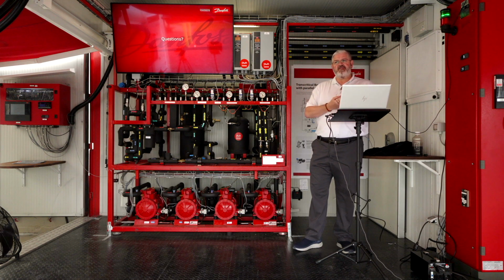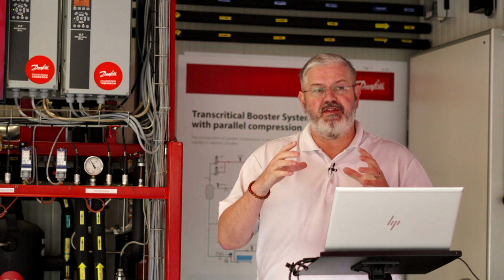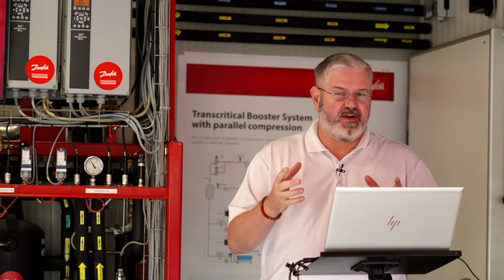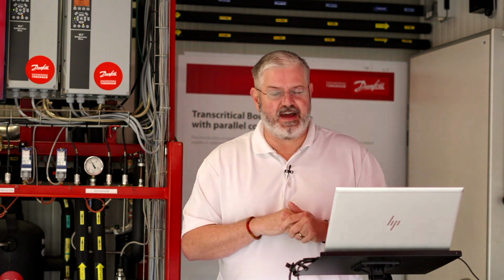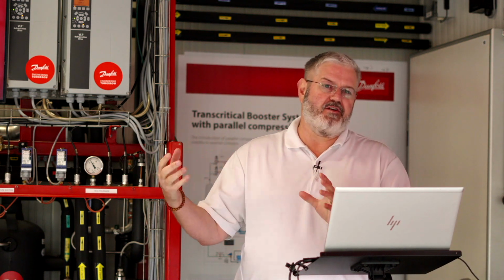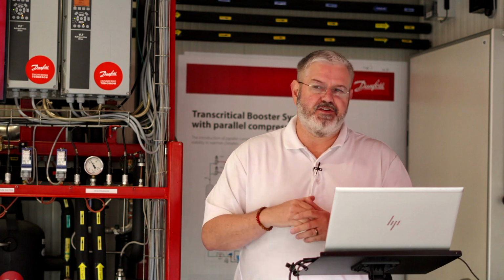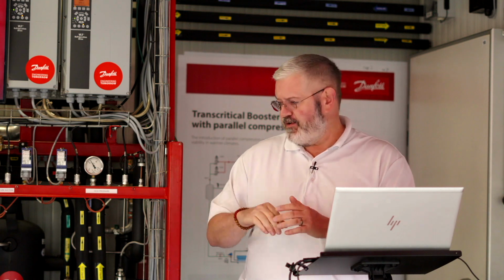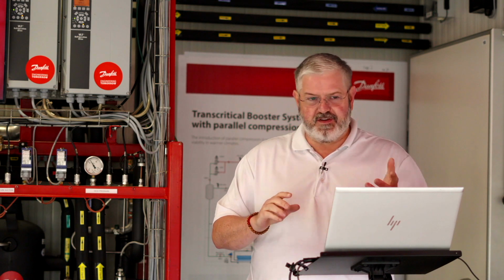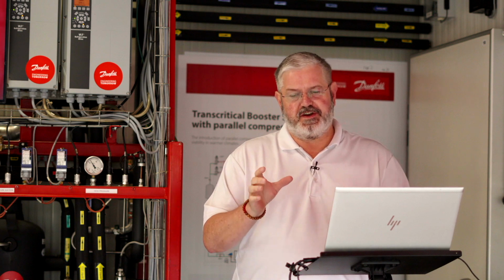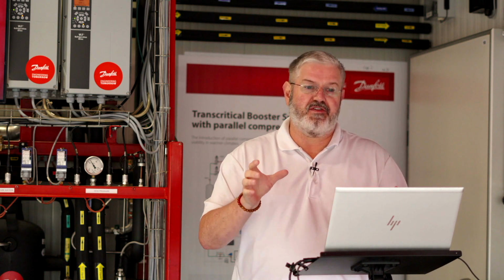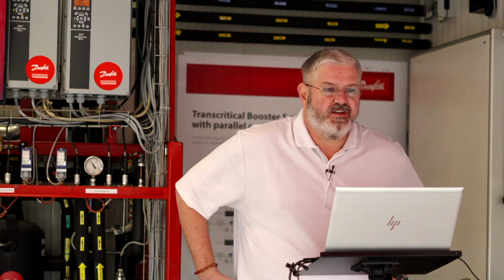But you're basically going to do a calculation by people smarter than myself, and they're going to determine the amount of flow that will be a gas or that'll flash off in high ambient, and you'll size the parallel compressors for that amount. So you're going to size them based on the system load. And to answer the question simply, there wouldn't necessarily be a relationship between number of compressors. Hope that answers your question.